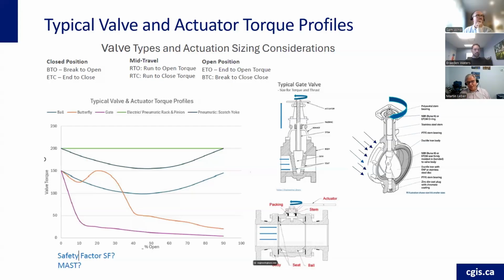Really the manufacturer needs to confirm what the maximum stall of the actuator is. There are some guidelines, and typically it's 2 to 1, meaning that if an actuator is rated for 100 foot-pounds unseating torque, then the stall could be 200 foot-pounds. But every manufacturer is different, and Limitorque actually provides technical data on the stall of their actuators, so that's what you go by. Awesome. Okay, thank you.